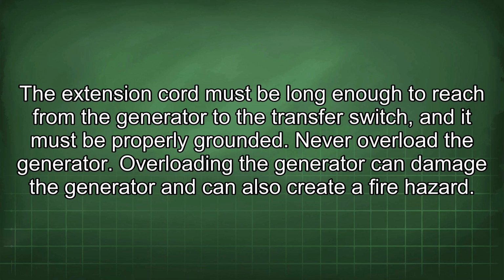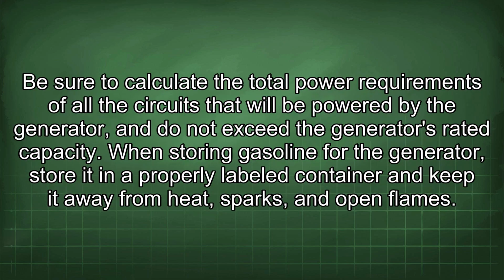Never overload the generator. Overloading the generator can damage the generator and can also create a fire hazard. Be sure to calculate the total power requirements of all the circuits that will be powered by the generator, and do not exceed the generator's rated capacity.